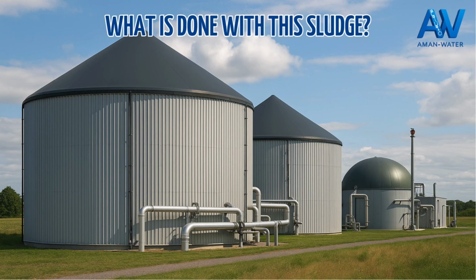The second pathway is energy recovery. Digested sludge produces biogas, a mixture rich in methane. This gas can power generators to produce electricity, heat, or even be purified into biomethane for injection into the gas network. Some treatment plants reach a very high level of energy autonomy through this pathway, significantly reducing their carbon footprint.